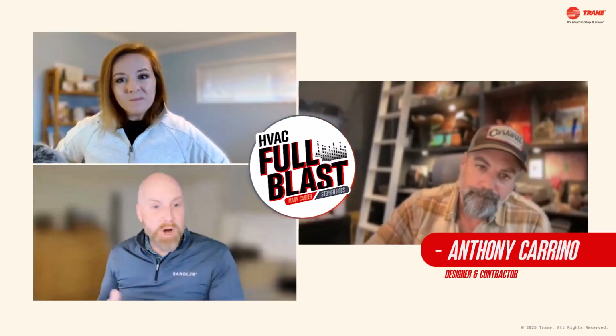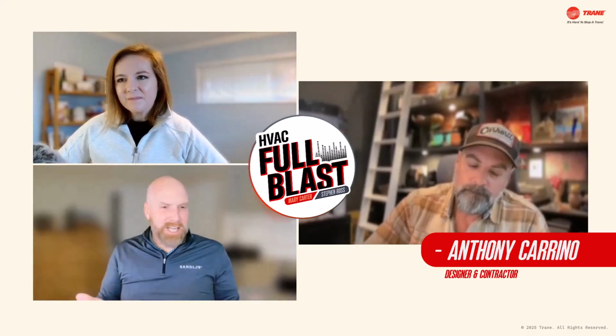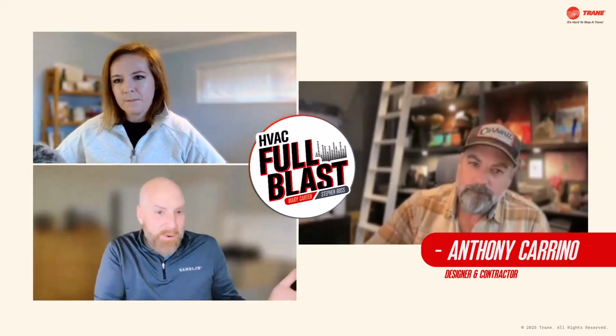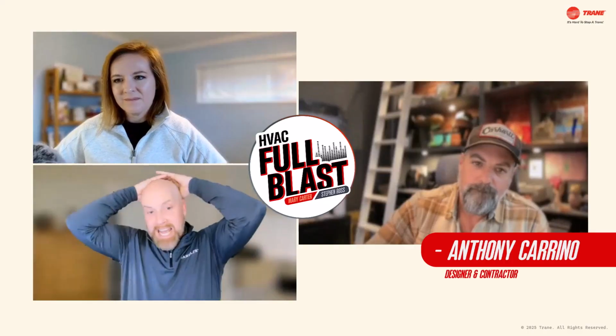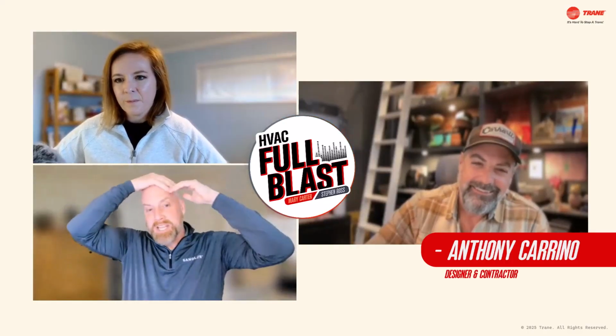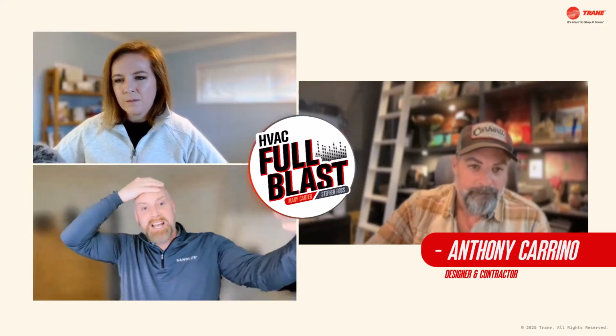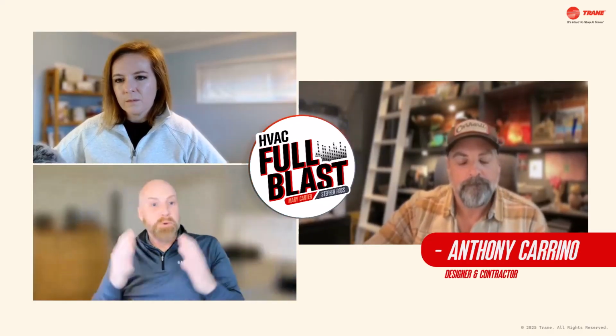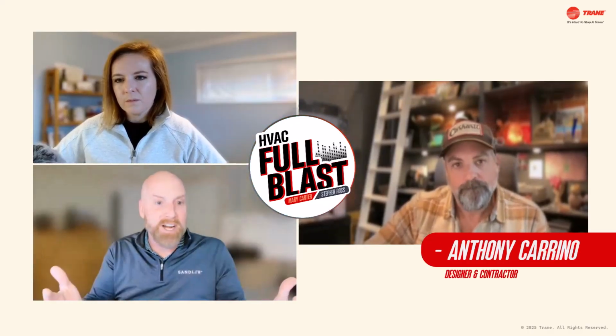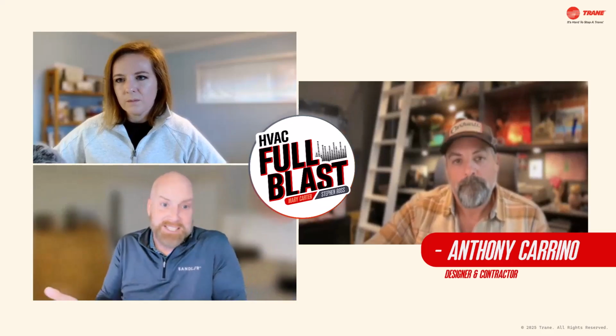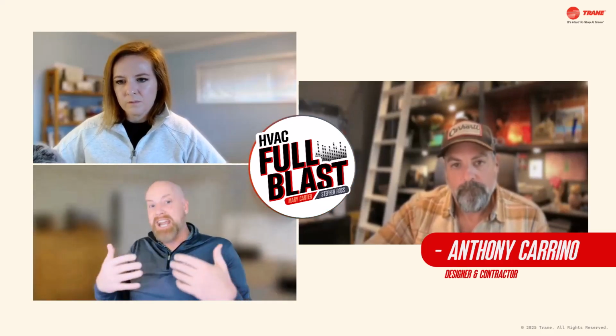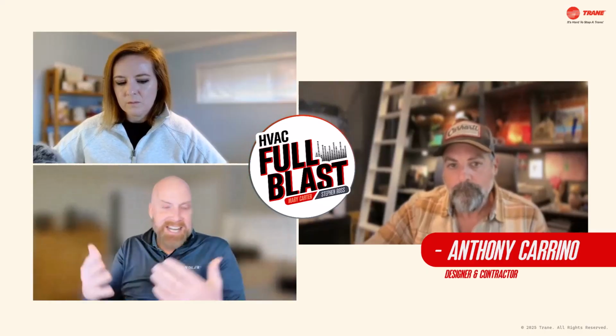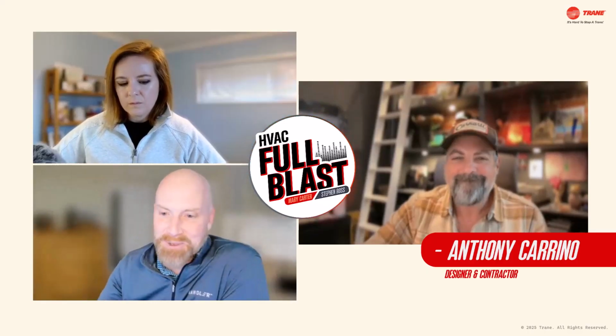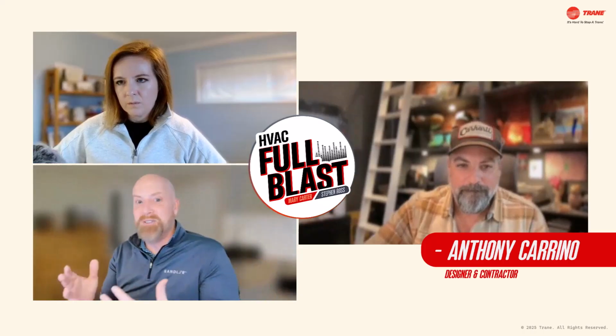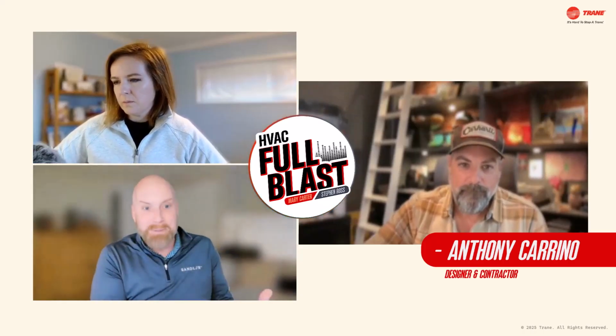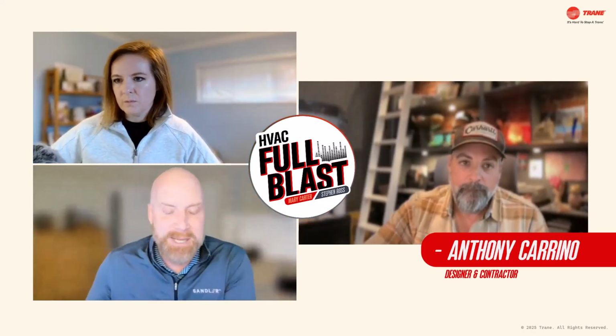In that scenario, the homeowner, we pushed back a little bit to the builder - why do you have a dining room this big? And they said, hey, we plan on entertaining. So to your point, we did have to oversize the equipment a little bit. We went with 2 systems instead of just 1, but put in variable speed systems that could ramp back down. Because even though they're saying they host people regularly, it's still not that many hours of runtime. It's just that when it happens, it's a real big deal if the heating and air can't keep up.